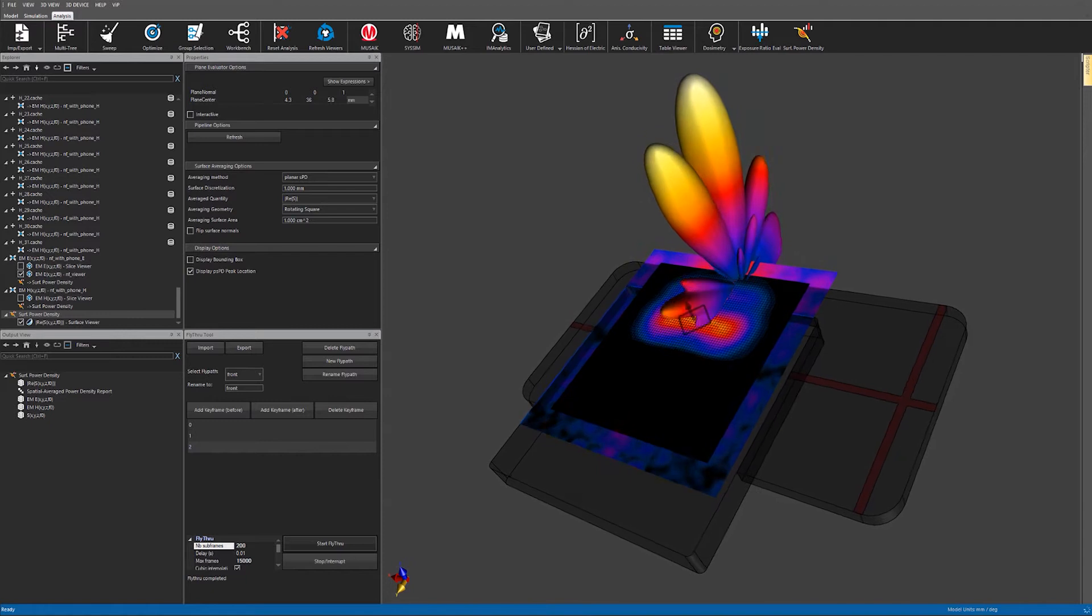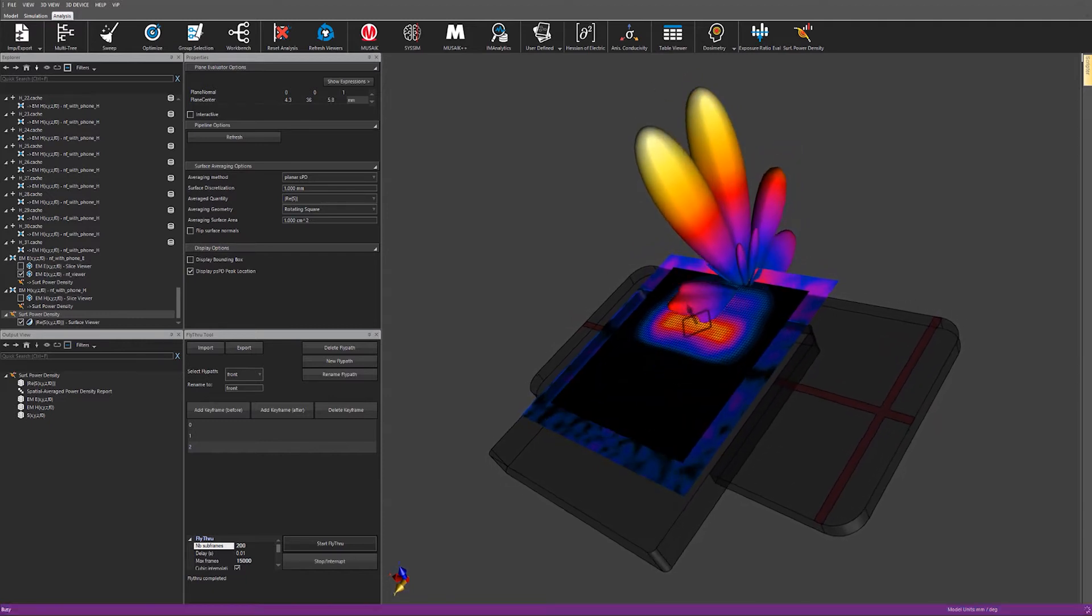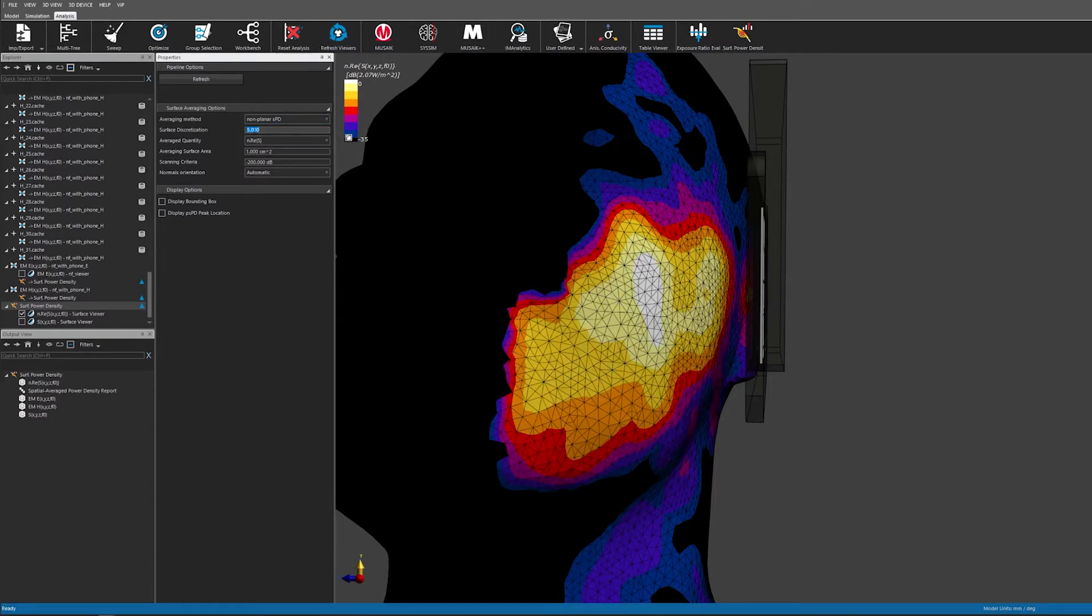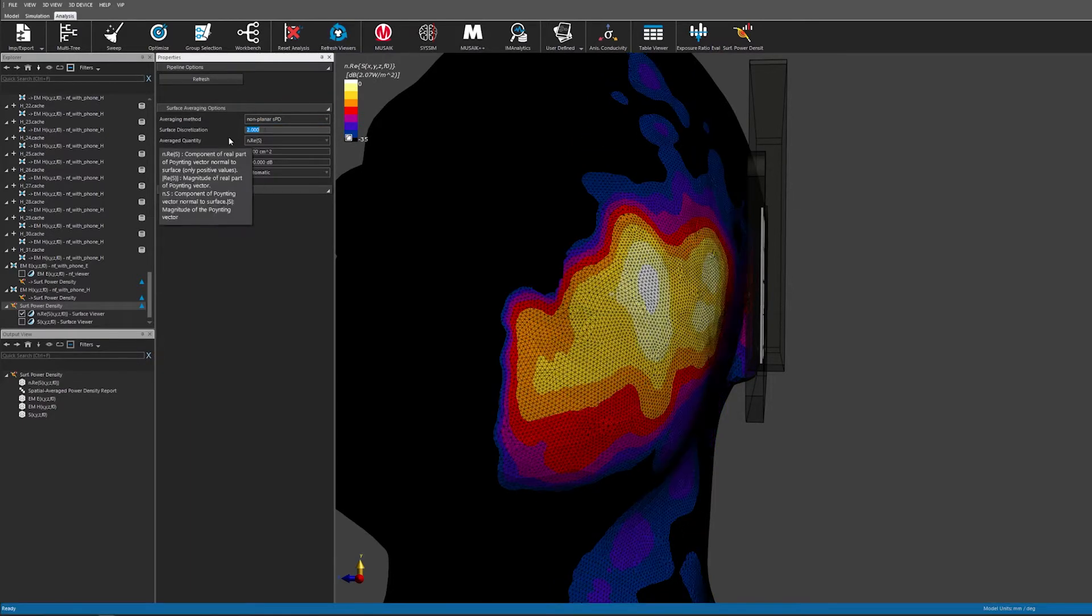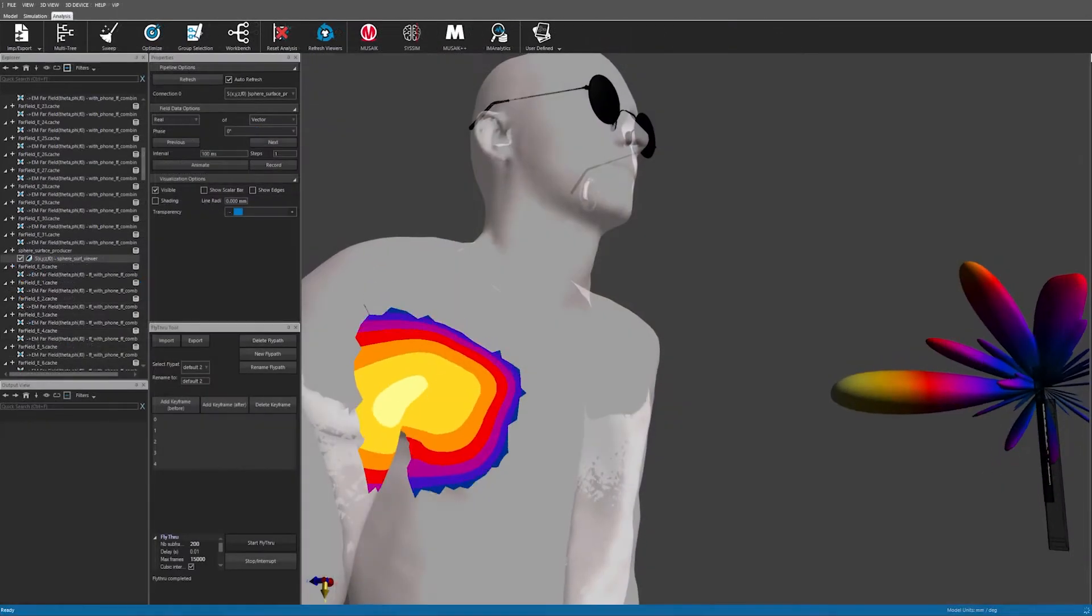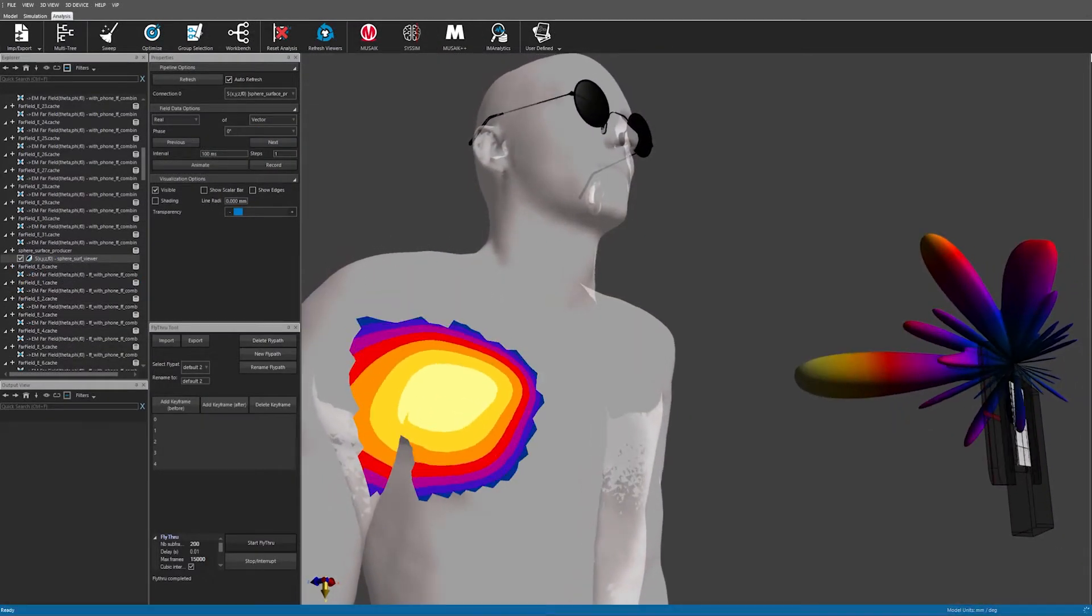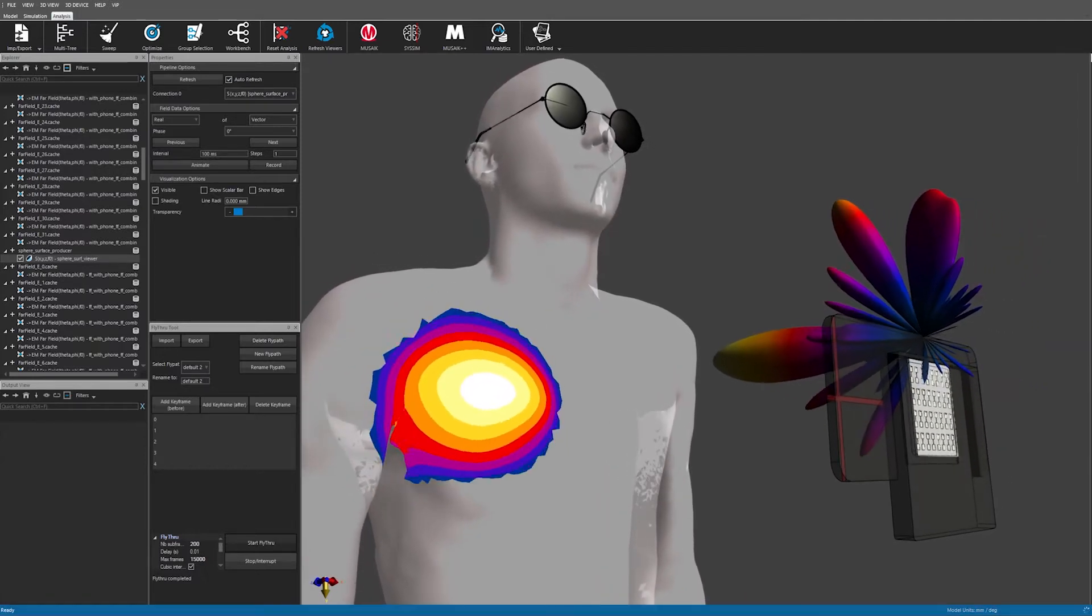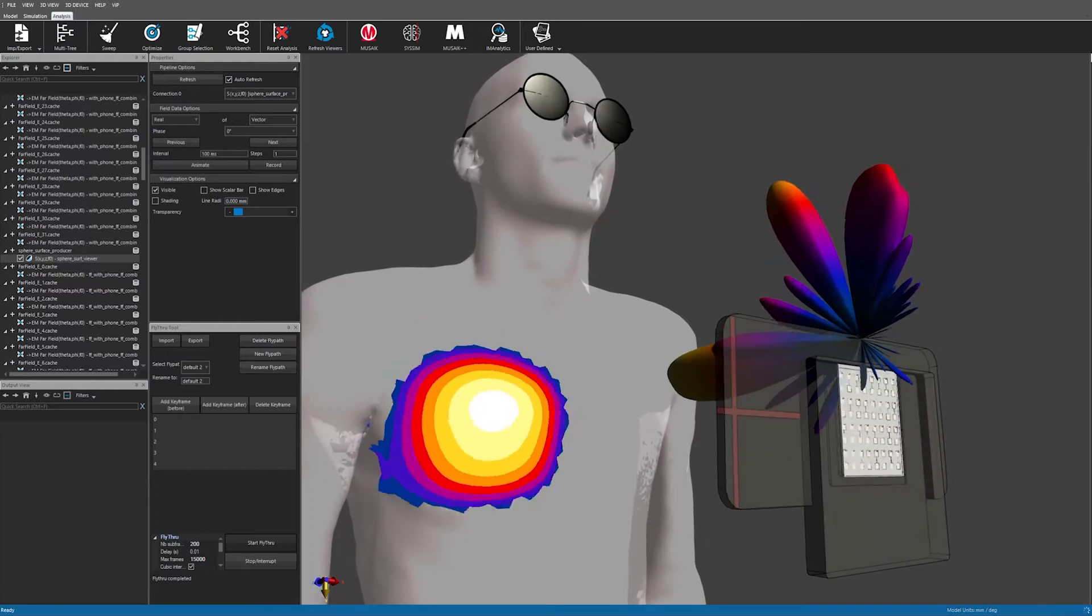The evaluator can also be used on curved surfaces like on the SAM head here. It is also fast enough to use on large surfaces, for example, the skin of an anatomical human model. We can clearly see where the beam is impinging the body here.